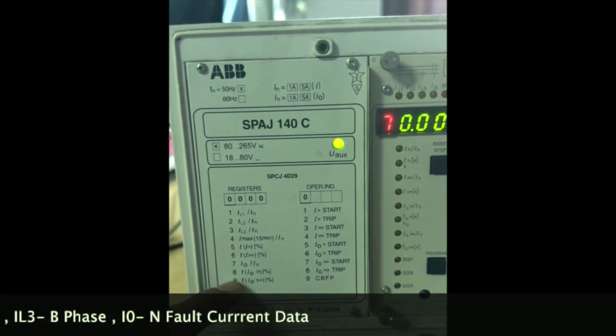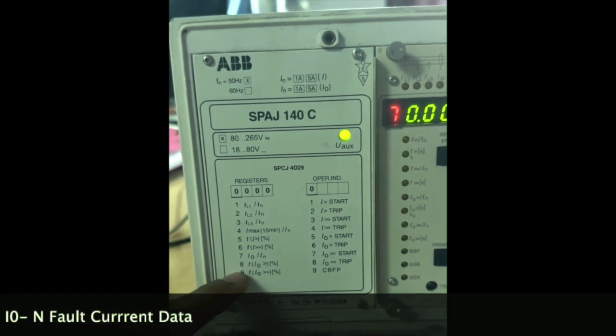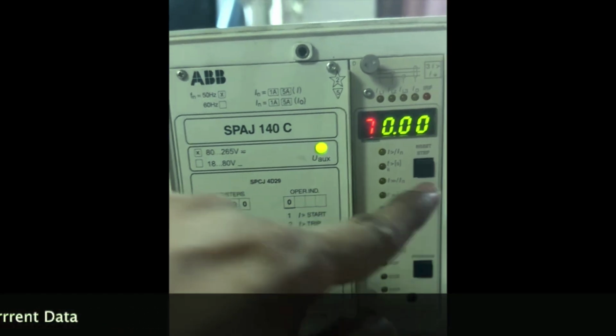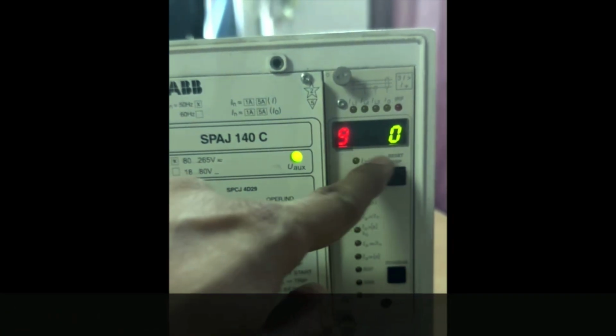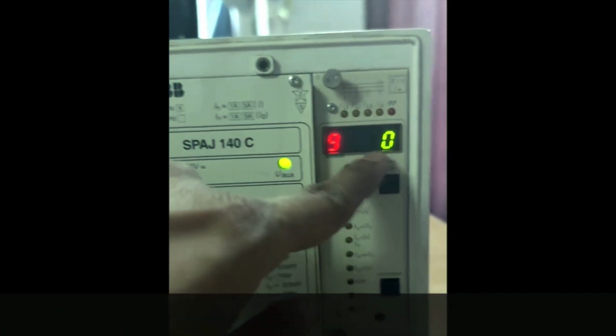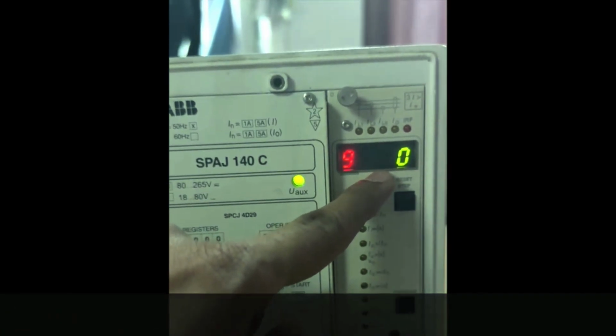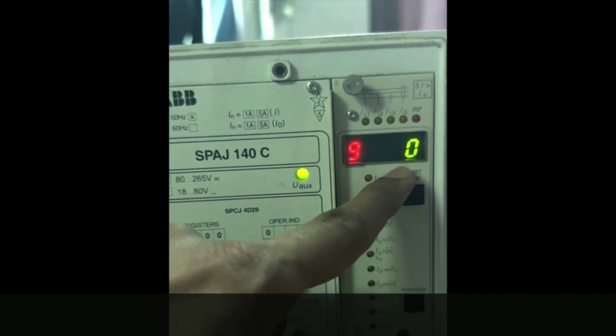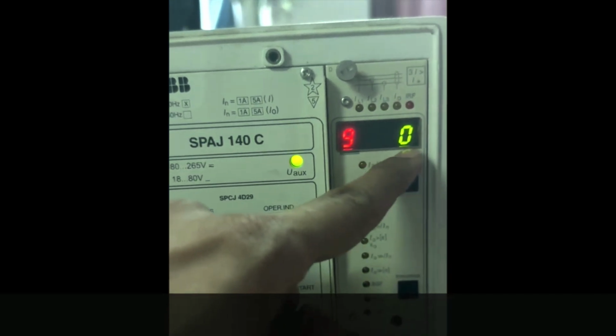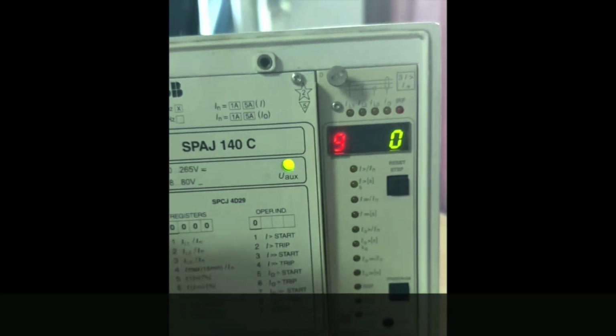Now suppose I also want to check if my relay is operating in the high setting. For that, if you get 100%, that means it's operating completely on the high side. If it shows 70% or 60% here, it means the relay has not fully operated on the high side.